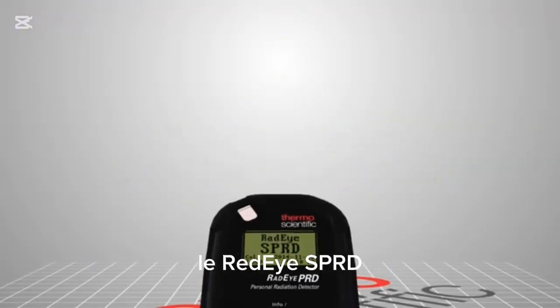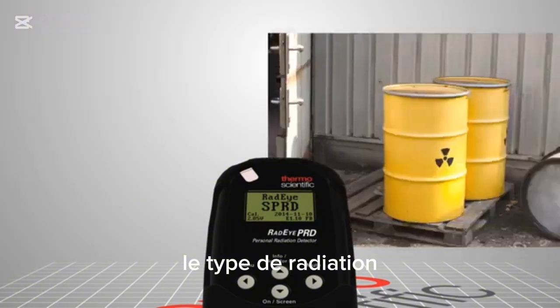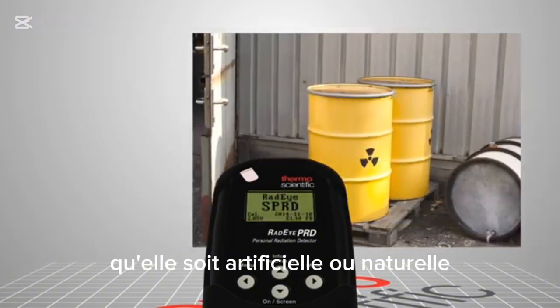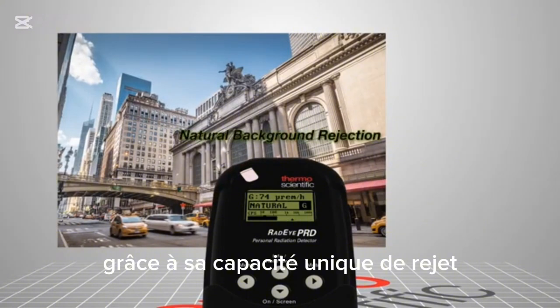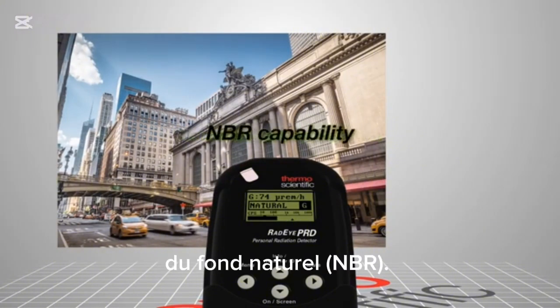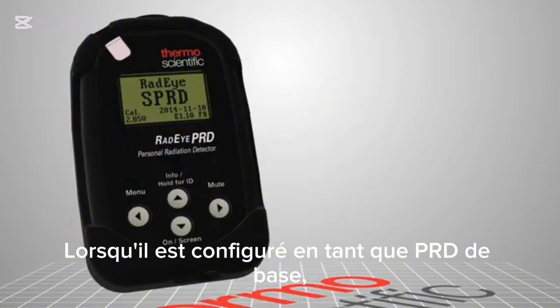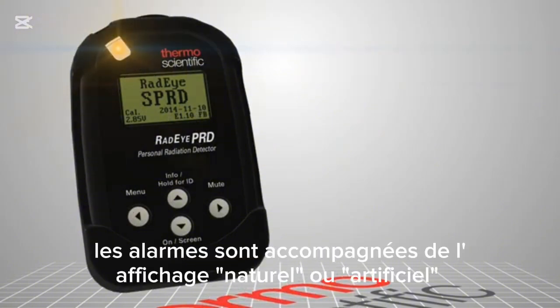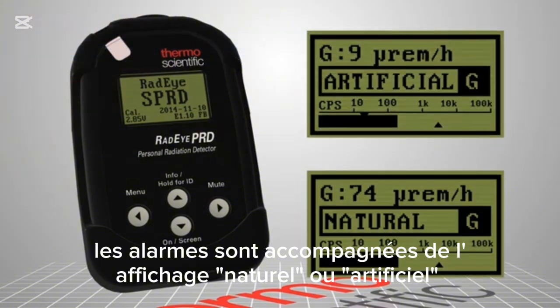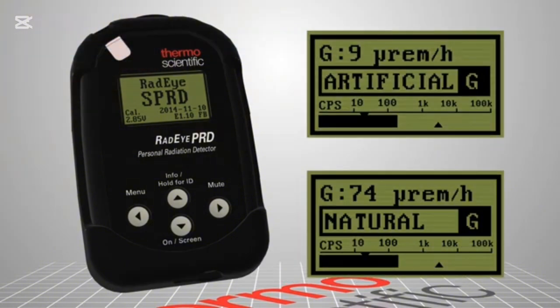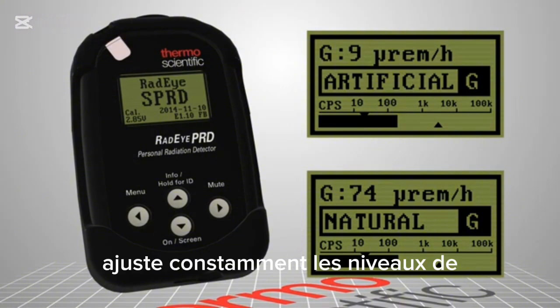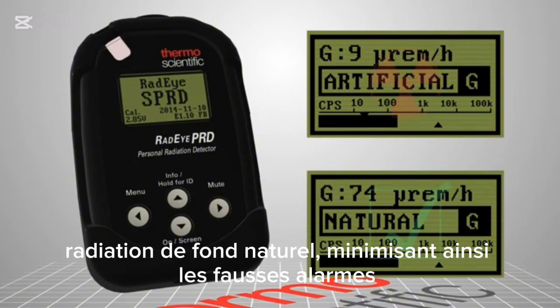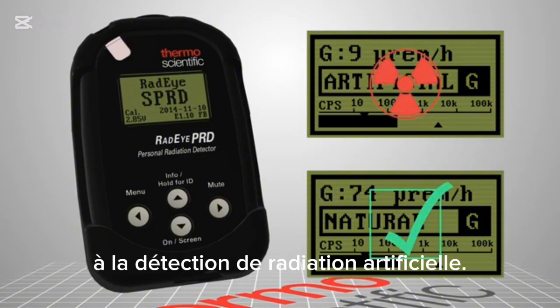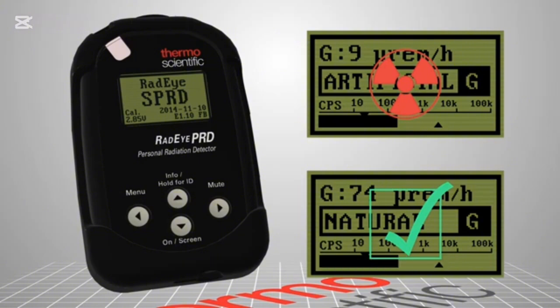The RadEye SPRD automatically determines the radiation type as either artificial or natural with its unique natural background rejection, or NBR, capability. When configured as a basic PRD, alarms will be accompanied with either natural or artificial displayed on the screen. The unit constantly adjusts to varying levels of natural background radiation, which minimizes false alarms while maintaining detection sensitivity for artificial radiation.